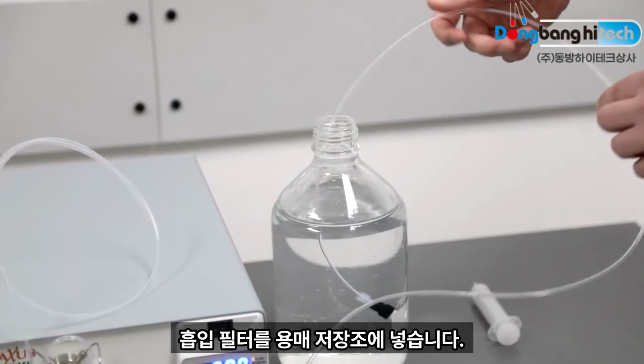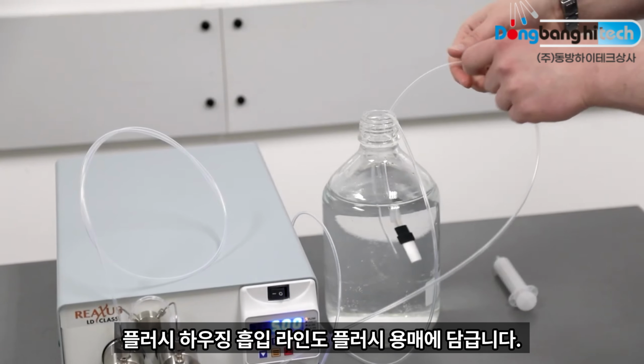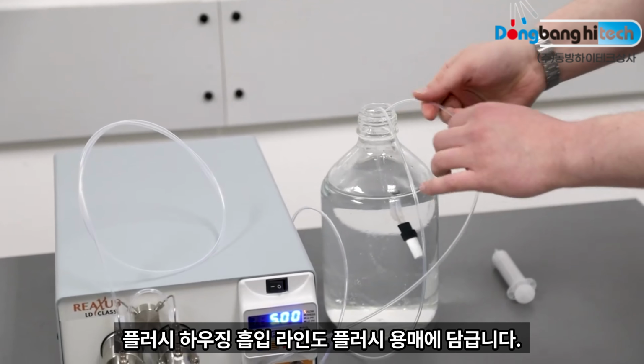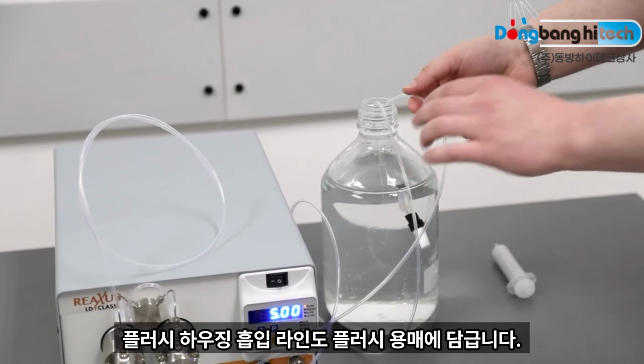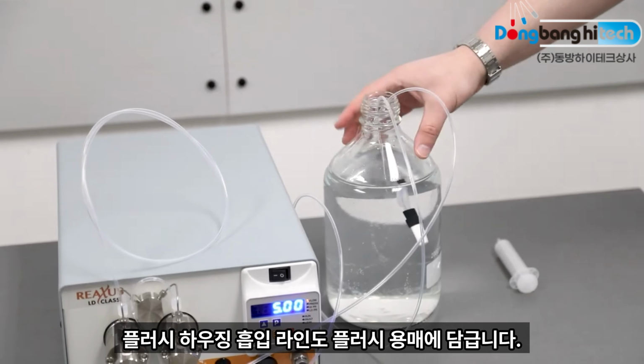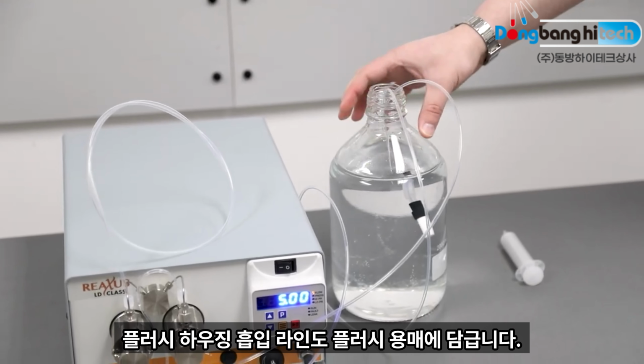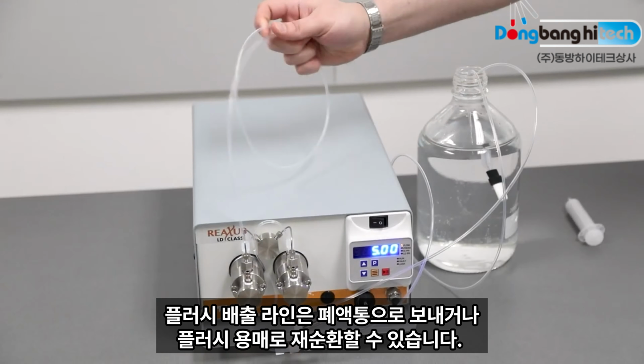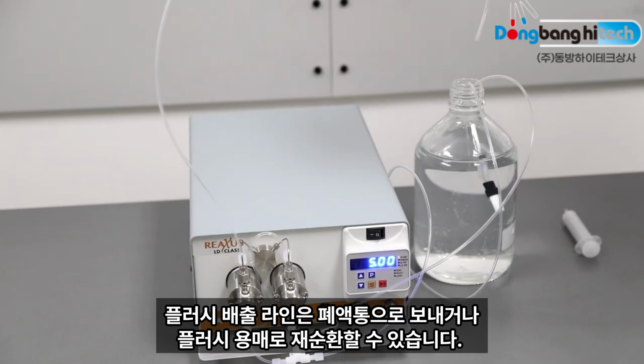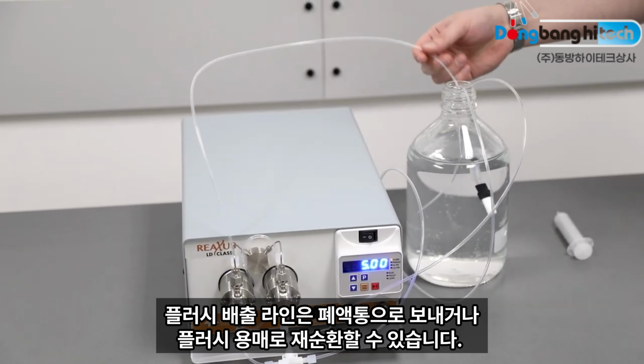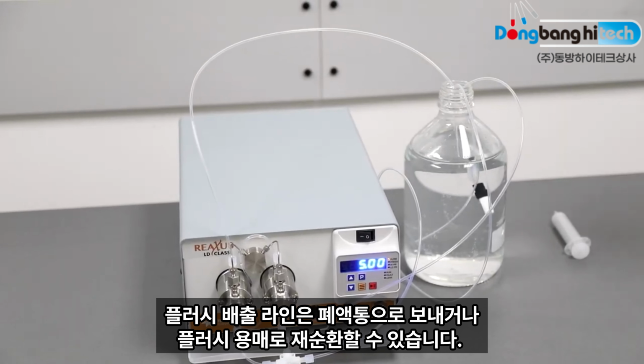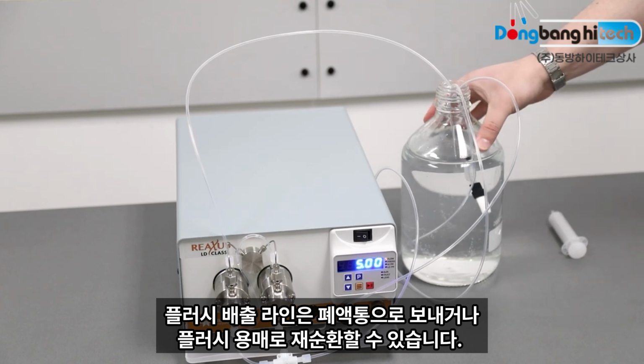Now that we have our tubing installed, we can go ahead and insert our inlet filter into our solvent reservoir. We can also drop the inlet to our flush housing into your flush solvent. Again, in this demonstration, we'll be using the same solvent that we'll be pumping through the system. I will also want to place my outlet either to waste or back into your wash solvent, your flush solvent, to recycle through.